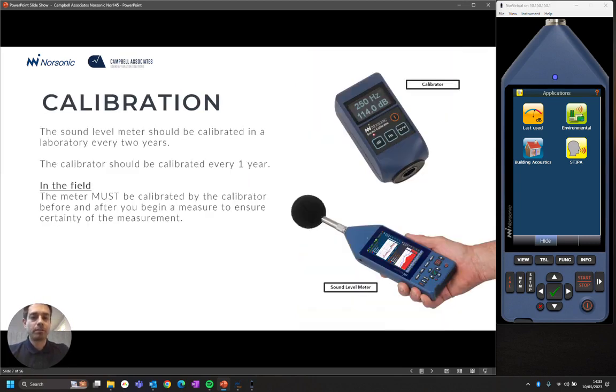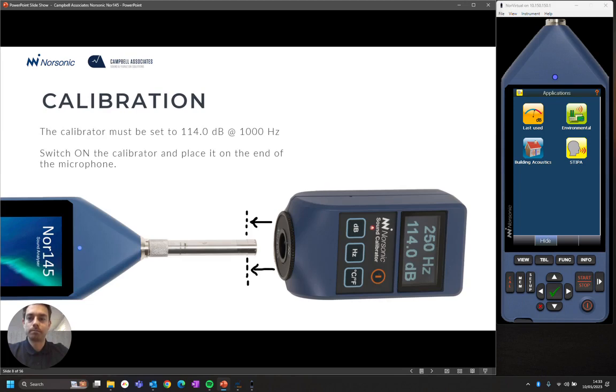The calibration intervals for the equipment: the sound level meter should be calibrated every 2 years. Let us know, we can actually remind you of this. And the calibrator is every 1 year. You must calibrate the instrument with the calibrator at the start of the measurement and at the end of the measurement to ensure certainty of the measurement.